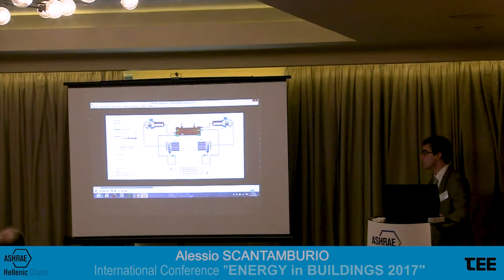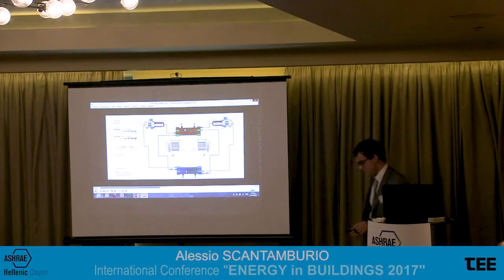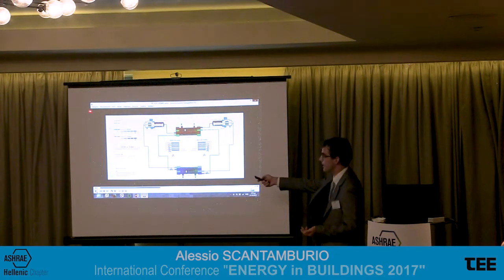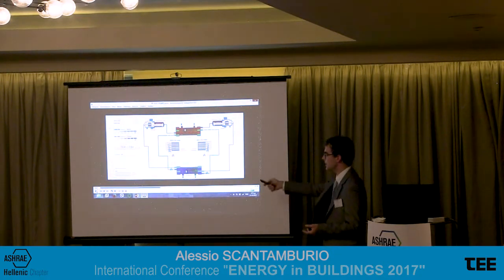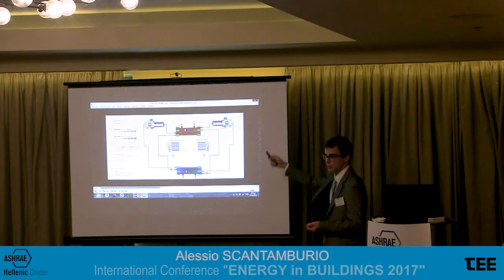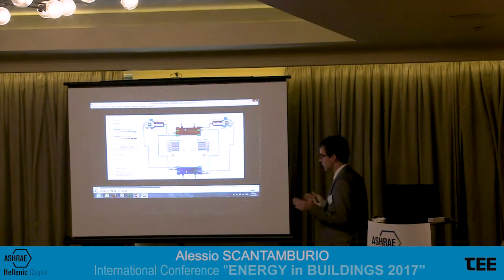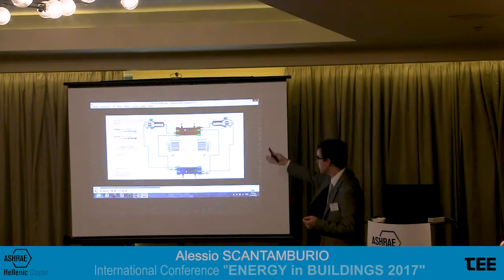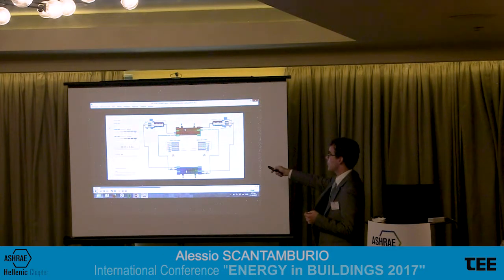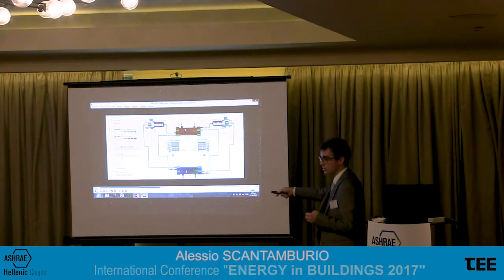But of course, a four-pipe unit must work in four-pipe mode, so producing cold water and hot water at the same time. And this is the case. This is only to show you because this is a particular case. It is really difficult that in reality the building requires 100% and 100% on the water side. It is a very lucky situation, but just to have an idea of how the refrigerant circuit works. In this case, we are requiring total capacity in these circuits, so we are not using the auxiliary exchanger. We are condensing all the refrigerant inside the main condenser and evaporating all the refrigerant inside the main evaporator, producing hot water and cold water at the same time.